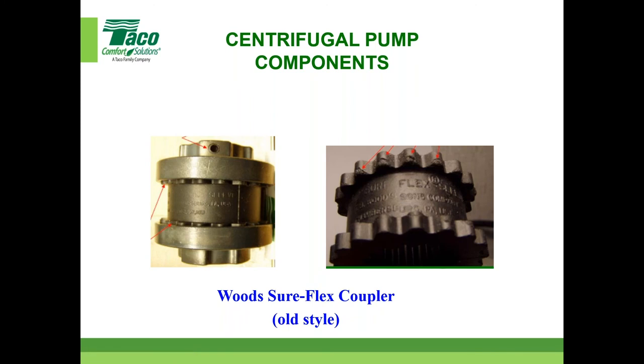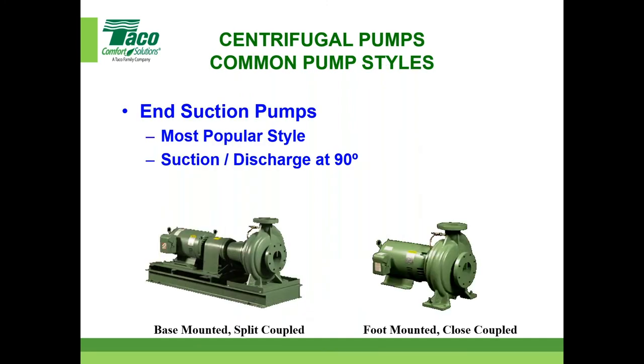So we've chosen to go with the other style. But just so you are familiar with them both, I'm sure they both work if they're designed correctly, and other people may use them, but we've standardized on the other ones. So just keep that in mind. Most popular still is the end suction, base mounted. There's the split coupled. There's the close coupled. What do I mean by close coupled? Again, the motor shaft is the impeller shaft. Here, the motor shaft has a coupler between it and the shaft that ties into the impeller.